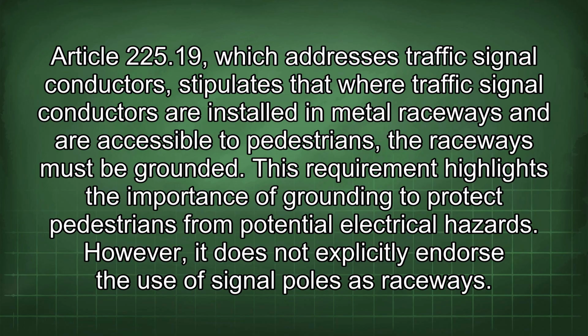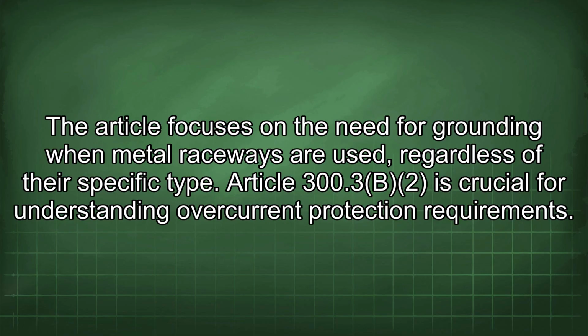Article 225.19, which addresses traffic signal conductors, stipulates that where traffic signal conductors are installed in metal raceways and are accessible to pedestrians, the raceways must be grounded. This requirement highlights the importance of grounding to protect pedestrians from potential electrical hazards. However, it does not explicitly endorse the use of signal poles as raceways. The article focuses on the need for grounding when metal raceways are used, regardless of their specific type.